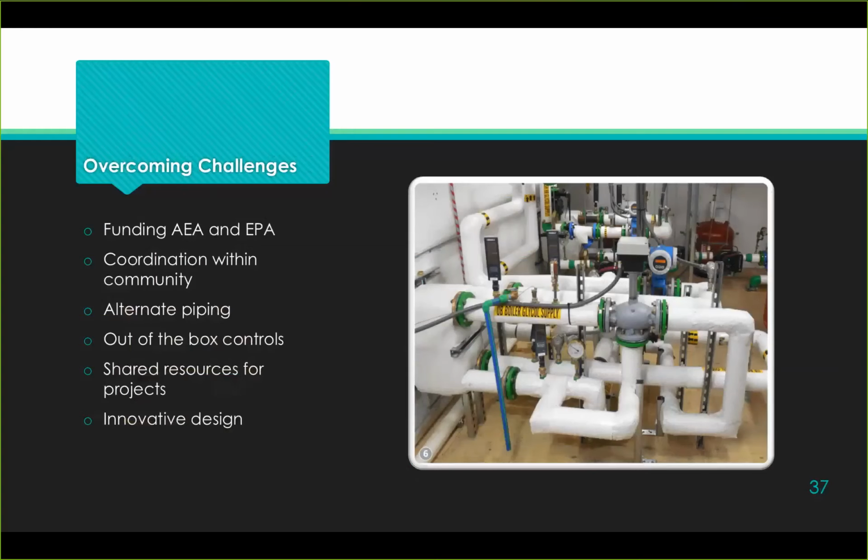Couldn't afford the cost to get it out to the community and use it. And PEX pipe, because we were serving a Washateria that had 200 degree water at it, we struggled with the fact that PEX pipe just wasn't going to give me the quality heat I needed out to the Washateria. So we came up with alternate piping sources.